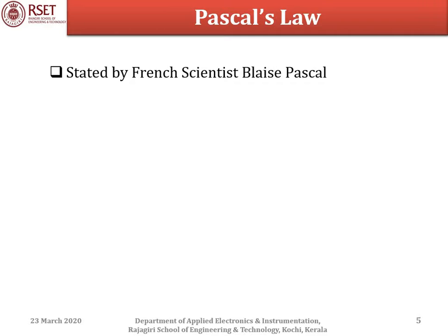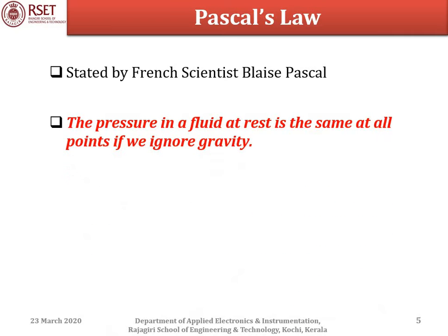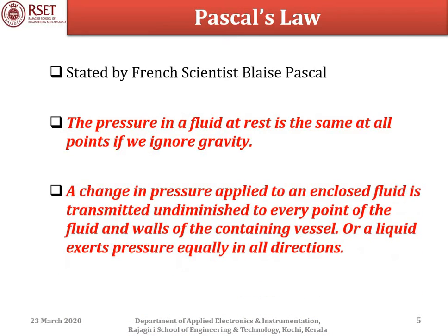The deadweight calibrator operates on Pascal's law, stated by French scientist Blaise Pascal. The pressure in a fluid at rest is the same at all points if we ignore gravity. The change in pressure applied to an enclosed fluid is transmitted undiminished to every point of the fluid and walls of the containing vessel, where a liquid exerts pressure equally in all directions. This second definition is more relevant to the deadweight calibrator.